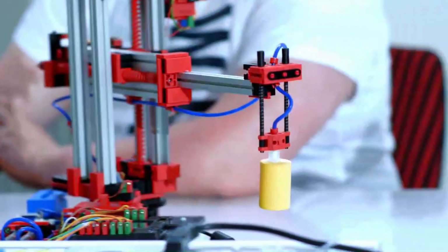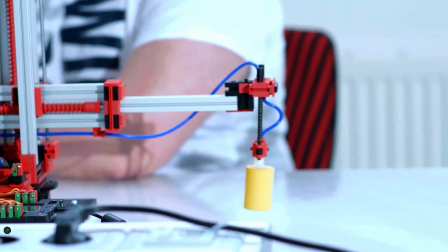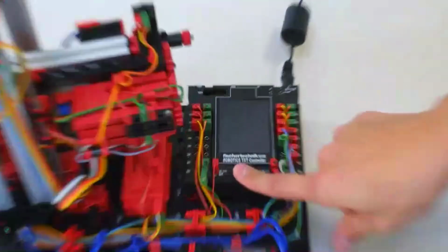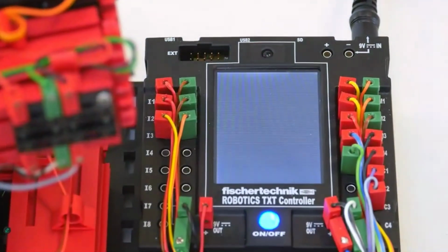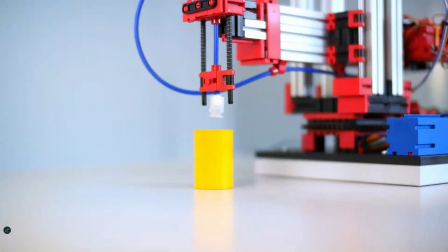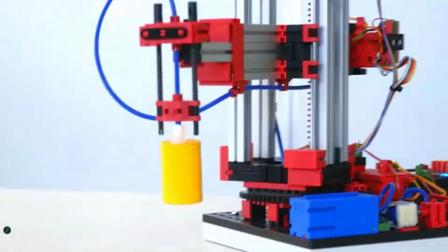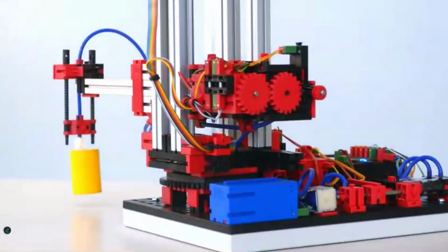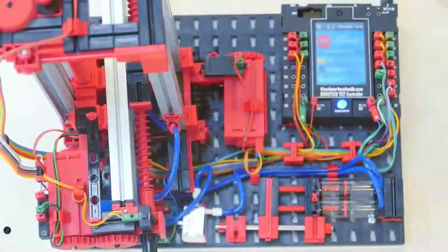And the 24-volt version of this model, as well as all of the 24-volt models we're going to be looking at moving forward, each have a relay board for motor polarity reversal and a multi-pin connector. And in this case, and moving forward again, 34 pins with a grid of 2.54 millimeters, as well as additional PCB terminals with push connections for all inputs and outputs.